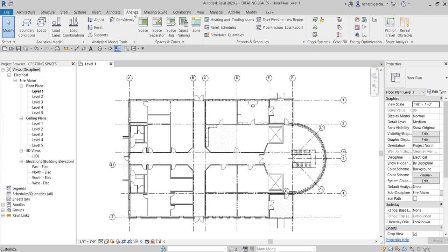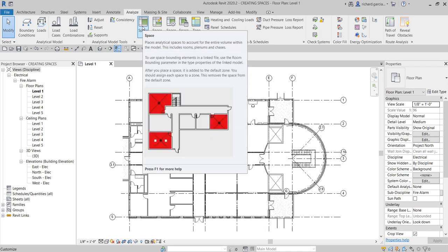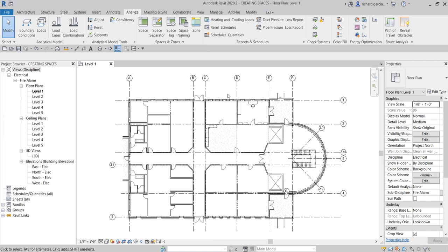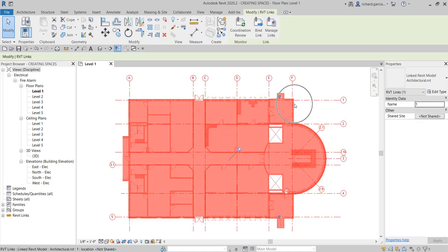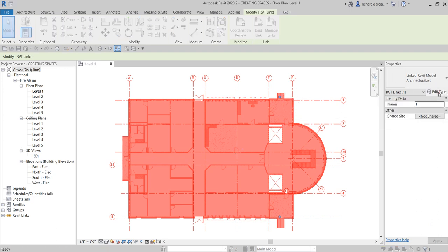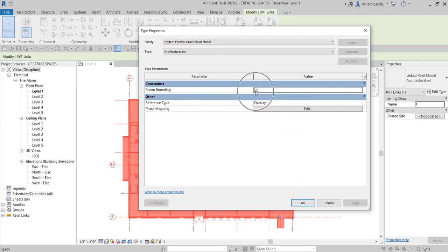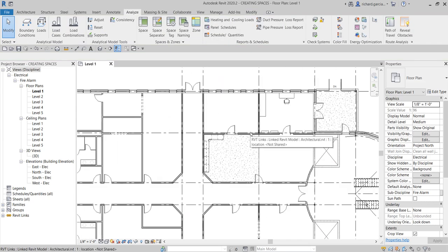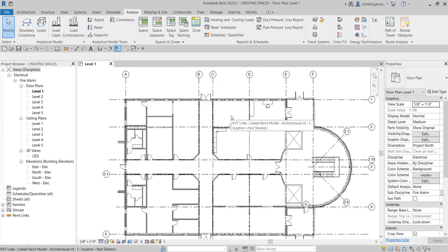To place a space, go to the Analyze tab. You'll see the Spaces and Zones panel with the Space tool. Before placing, remember that when we linked our architectural model in the first part of setting up our project, we selected our link model, went to Edit Type to open type properties, and checked the Room Bounding parameter. This is very important — if you do not check the room bounding parameter of your linked model, Revit will not detect the room bounding components and you will not be able to place your spaces correctly.